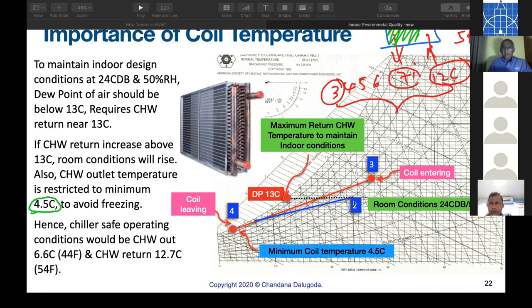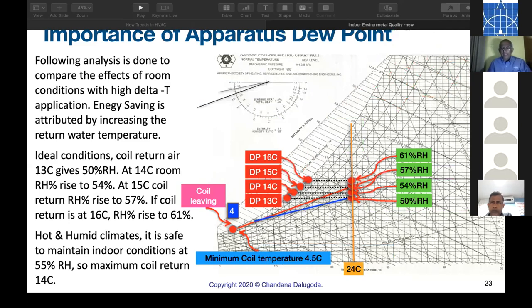So remember not to increase the chill water return temperature unnecessarily by raising the chill water supply temperature, that is chill water resetting, because that will affect the RH, the room RH. This is what happens when we raise the return temperature up. Say we are at 24 degrees C dry bulb, constant we will assume, and RH will be 50 when the dew point is 13.